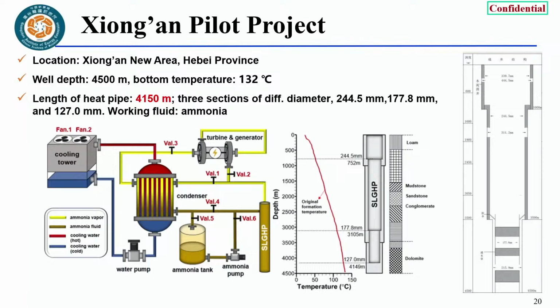And the second project is located in the Xiong'an new area of Hebei province, China. We utilize a 4,150 meters long heat pipe. This heat pipe was installed in the 4,500 meters deep well with a bottom temperature of 132 degrees Celsius. The heat pipe consists of 3 sections with different diameters and employs ammonia as the working fluid.